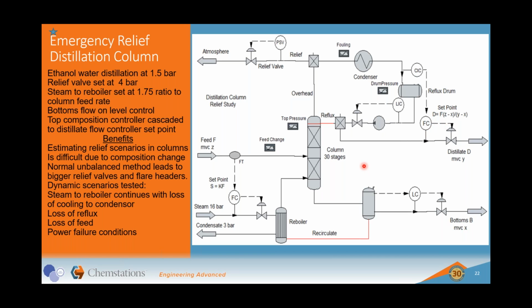So basically what's going to happen, we're going to run this at 1.5 bar, and then I'm going to drive the pressure at the top to relief pressure, which would simulate a blockage in the overhead situation.